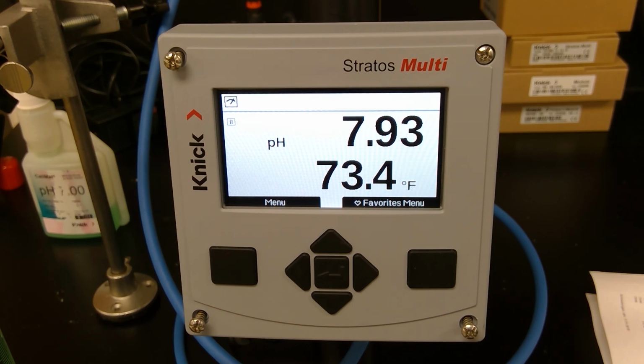So the idea with this type of technology is that you're able to do a process calibration, which effectively means you leave the probe in the process, you do not remove it. You take a grab sample, and then you have that grab sample analyzed, and that could be using a Portavo with a pH probe, measuring it, or taking the sample to the lab. So that way you have a known good value. And to do that, it's pretty straightforward.